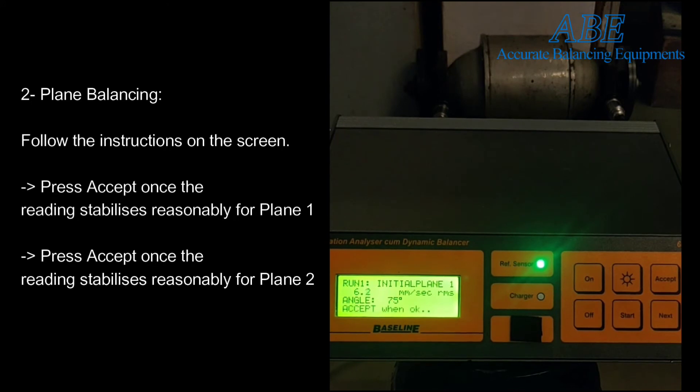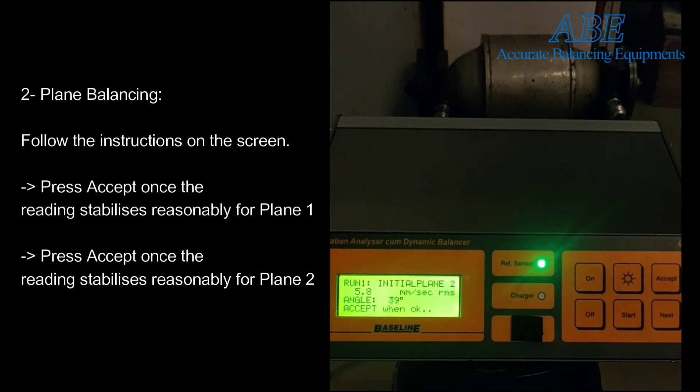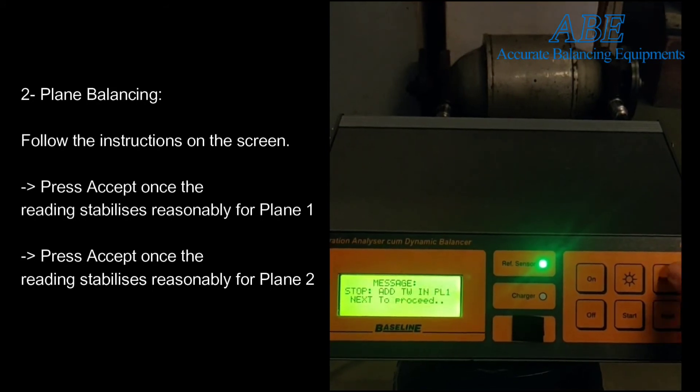After setting up the rotor, follow the instructions on the screen which will lead you to take the initial vector readings in plane 1 and then in plane 2. After that, stop the rotor and add the trial weight in plane 1.